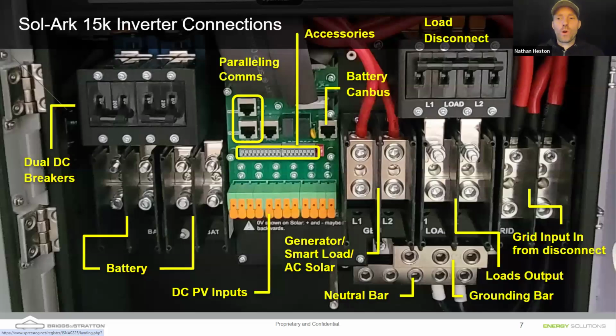This is not a talk about wiring, but here is the inside of a Sol-Ark 15K. On the left side of the screen are the battery inputs. So you have dual battery inputs. There's a single pole breaker on both of the positive inputs that's 200 amps. The Sol-Ark is only capable of drawing about 275 amp maximum from the batteries, but you have dual 200 amp breakers there, and that allows you to use smaller cabling. Typically, we'll see these connected with dual sets of 2-aught cable, dual sets of 1-aught cable. And that's a nice feature there.